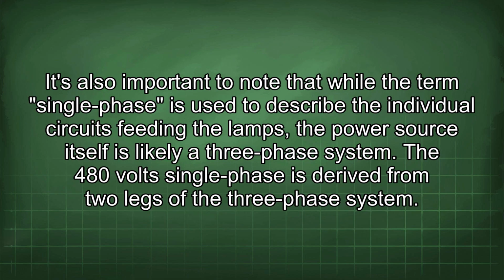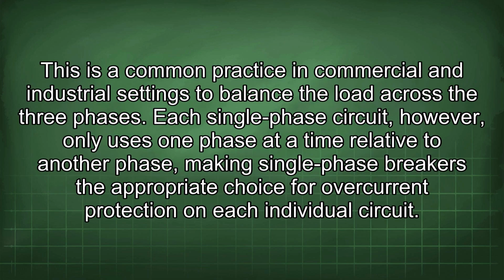It's also important to note that while the term single phase is used to describe the individual circuits feeding the lamps, the power source itself is likely a three-phase system. The 480-volt single phase is derived from 2 legs of the three-phase system. This is a common practice in commercial and industrial settings to balance the load across the 3 phases. Each single-phase circuit, however, only uses one phase at a time relative to another phase, making single-phase breakers the appropriate choice for overcurrent protection on each individual circuit.